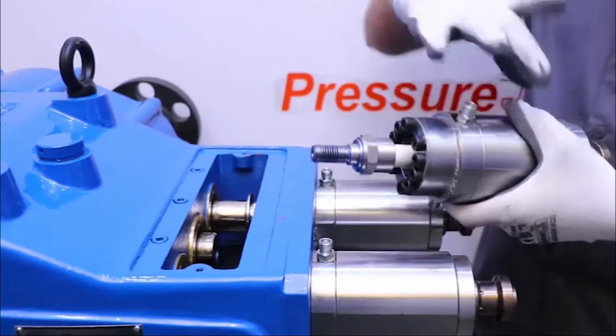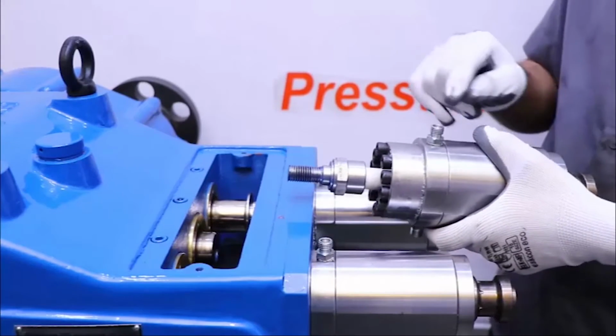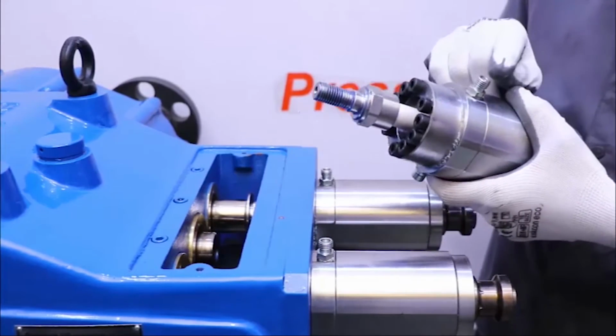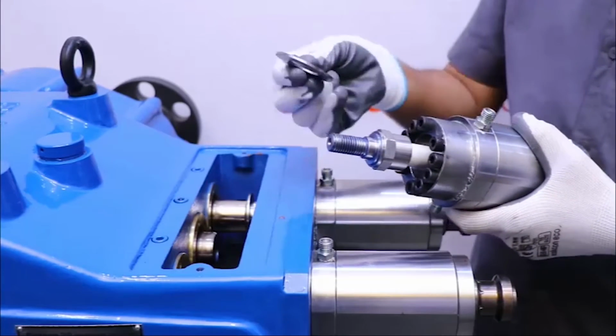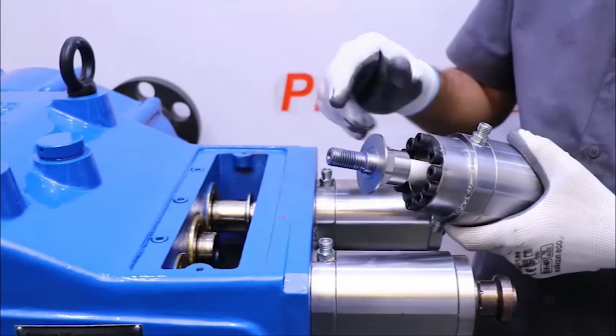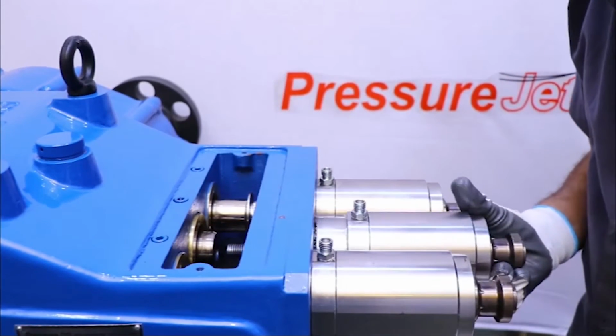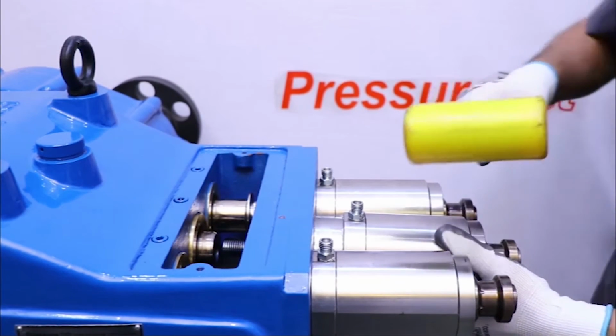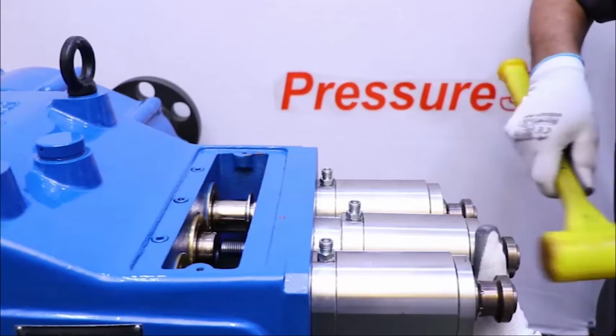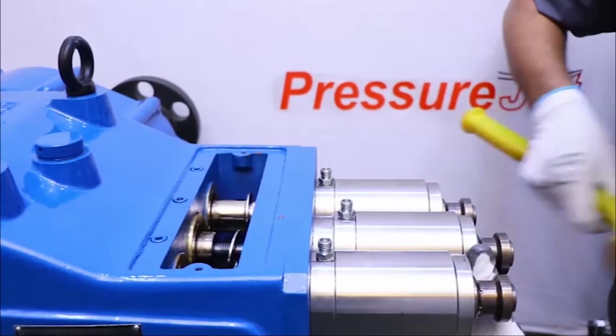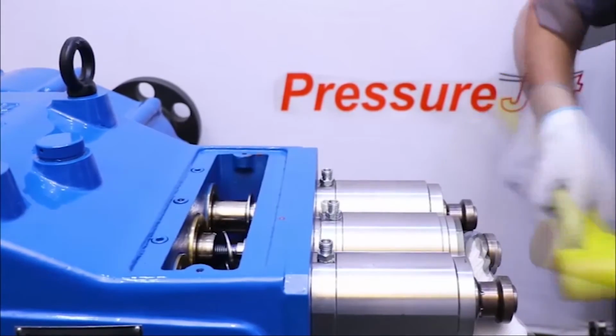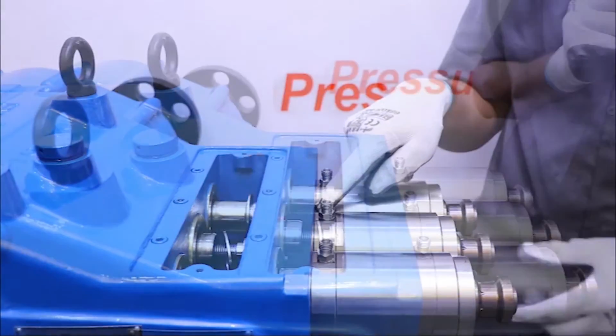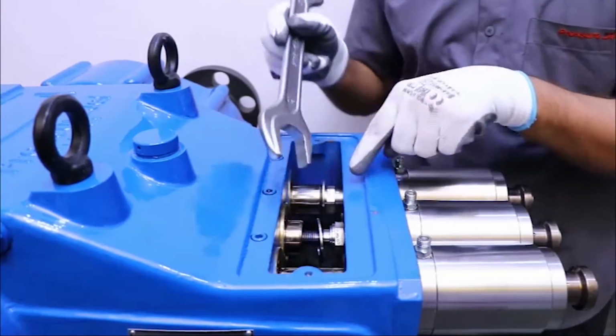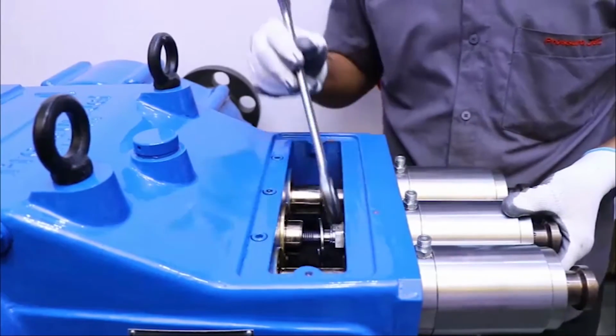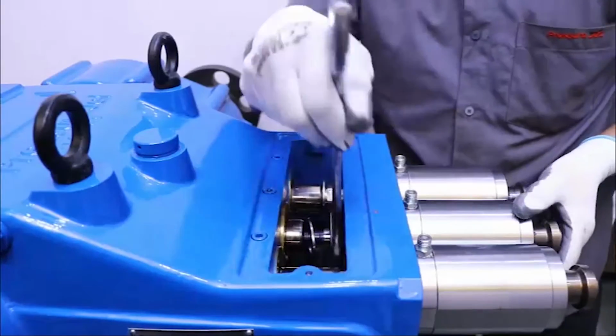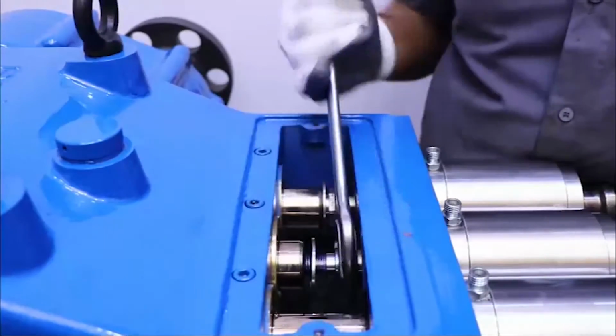Now assemble the stuffing box and plunger assembly inside the crankcase. The surface of the assembly will be matched with the crankcase surface and the cooling pipe connection will remain upward. Put the wiper in its position on the plunger. Place the assembly near its position and gently push using a rubber hammer to fix it in the proper position. After that, take a spanner and tighten the plunger inside the crosshead. Make sure it is properly tight.